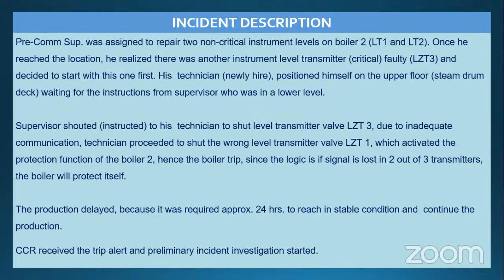This activated the protection function of boiler 2. As we explained, LZT1 and LZT2 were in operation, but LZT3 was faulty. The boiler was operating with LZT1 and LZT2. But due to the improper communication, the technician shut level transmitter LZT1. Now only LZT2 was in line with the boiler operation, which activated the protection function of boiler 2. Hence the boiler tripped, since the logic is that if the signal is lost from 2 out of 3 transmitters, the boiler will protect itself. LZT1 was isolated by the technician, LZT3 was already faulty, and the boiler was running with only LZT2.